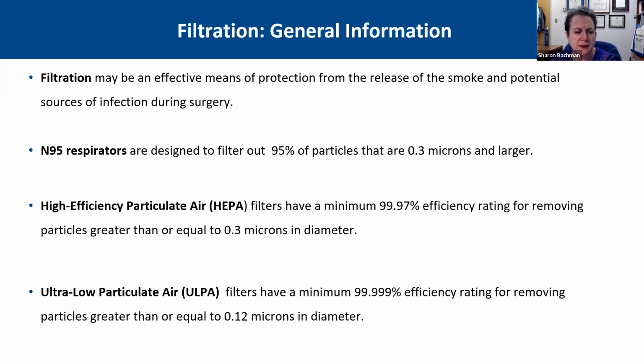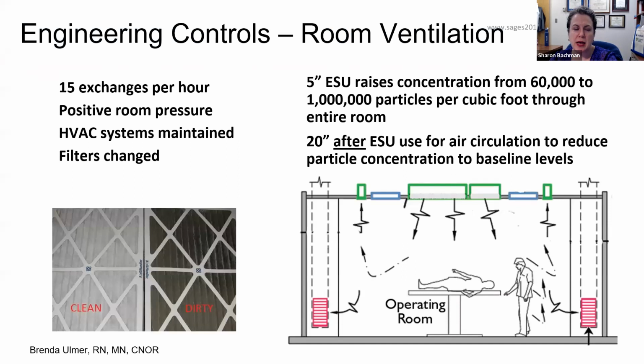Most people are also familiar with high efficiency particulate filters, so HEPA filters, which can filter out 99.9% of particles of that size, 0.3 microns. And then the ultra low particulate air filters are almost 100% efficient in removing particles that are 0.12 microns. For the top of that pyramid, this is really interesting because I hadn't really thought about this previously, but our ORs are mandated to have specific ventilation. For an OR to be compliant, it has to have 15 exchanges of the total room air per hour. That's why they're so noisy and you've got those big air handlers up in the ceiling. And those HVAC systems need to be maintained and filters changed. You can see that they do get dirty.